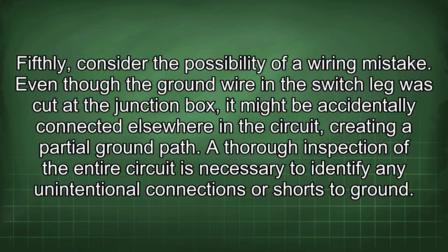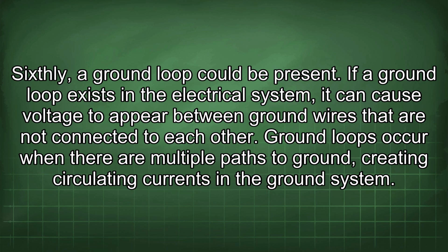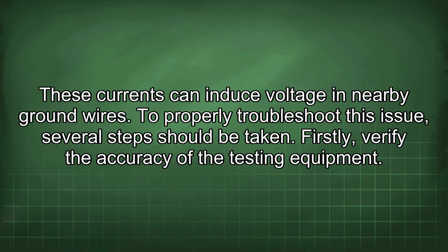Even though the ground wire in the switch leg was cut at the junction box, it might be accidentally connected elsewhere in the circuit, creating a partial ground path. A thorough inspection of the entire circuit is necessary to identify any unintentional connections or shorts to ground. Sixthly, a ground loop could be present. If a ground loop exists in the electrical system, it can cause voltage to appear between ground wires that are not connected to each other. Ground loops occur when there are multiple paths to ground, creating circulating currents in the ground system. These currents can induce voltage in nearby ground wires.